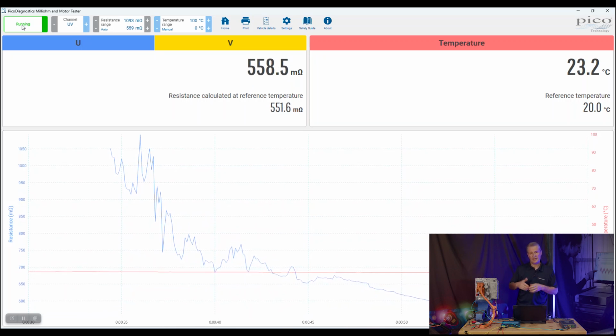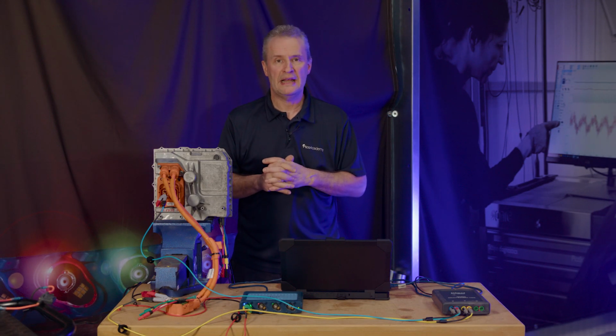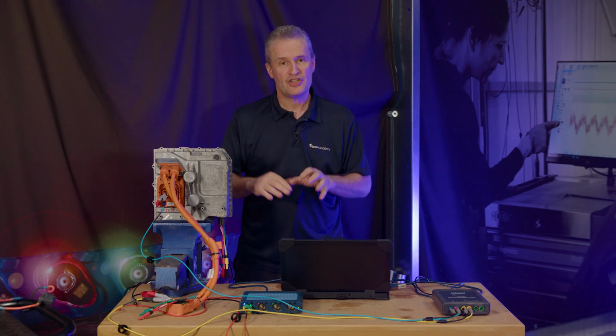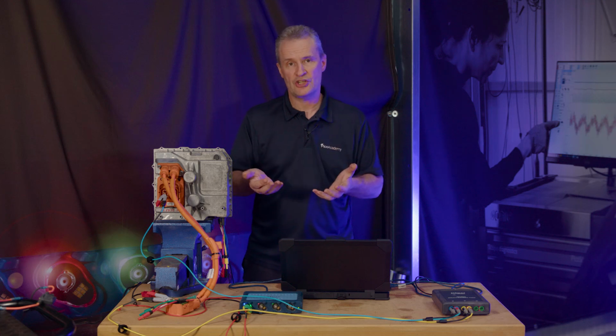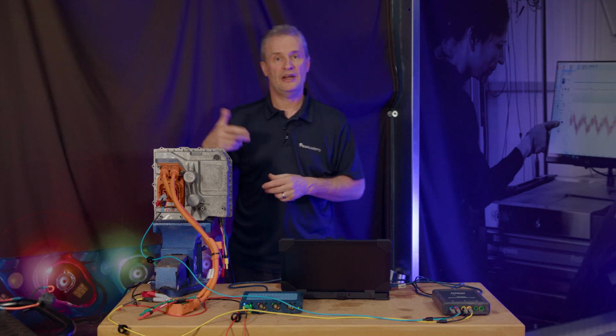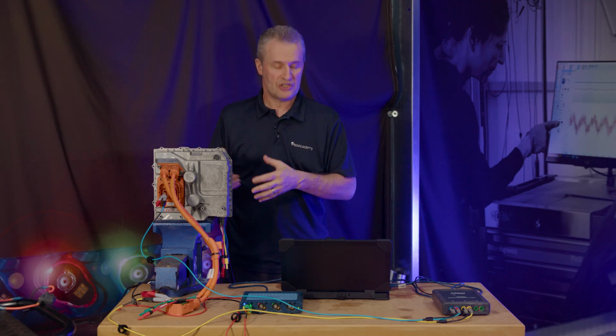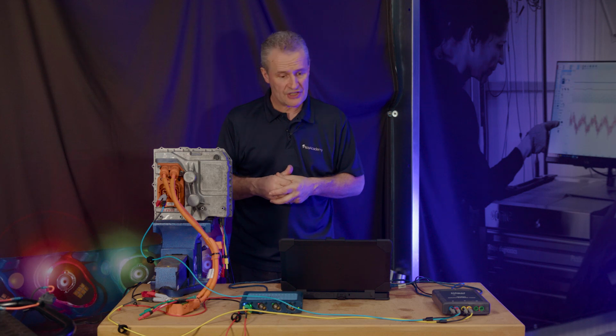Those contactors need to be replaced. Let's just think about that for a minute. 500 milliohm, that's half an ohm. It's a tiny resistance, but of course the voltage drop that you'll get across that kind of resistance when high current is flowing results in burning. And that's exactly what we've got here.